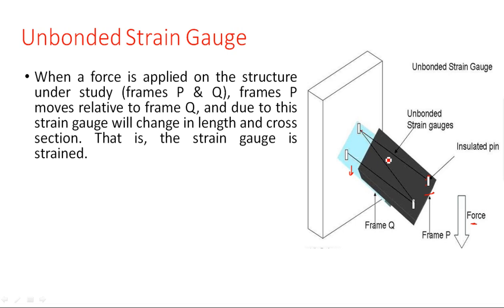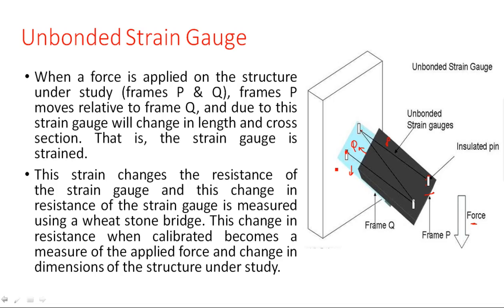Frame P and frame Q are connected with some gauge wire through the pins. When we apply some force either upward or downward, the gauge will expand or compress depending upon the movement of the frame, causing the resistance to vary. This change in resistance of the strain gauge is measured using a Wheatstone bridge, and when calibrated it becomes a measure of the applied force and change in dimensions of the structure under study.